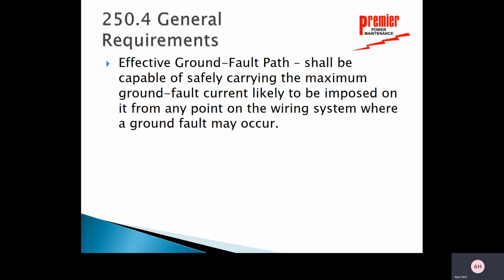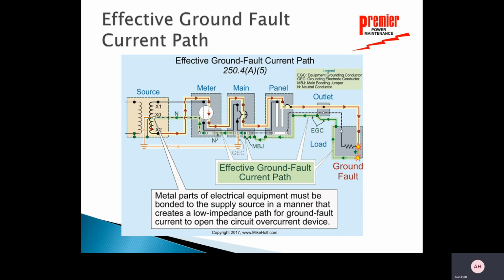Effectively, I want an effective ground fault path. So it's got to be capable of carrying the maximum ground fault current that's going to be imposed from time to time on any point in the wiring system if a ground fault occurs. So some consideration needs to be taken into the fact of how much ground fault can actually occur there. So let's look at an effective ground fault path.